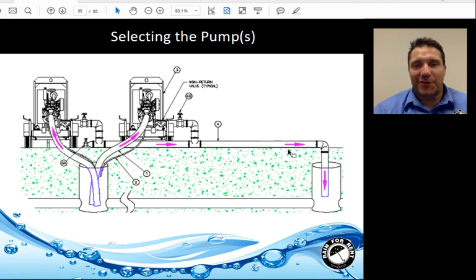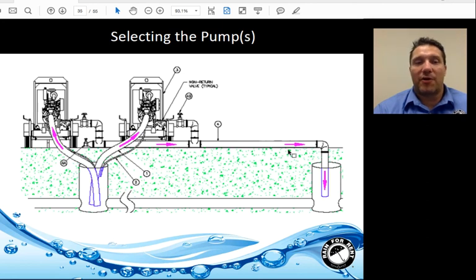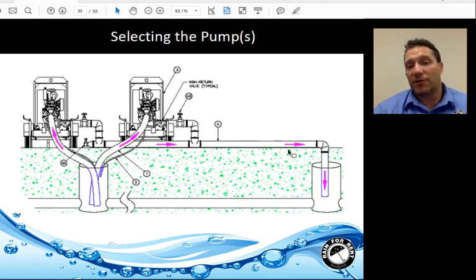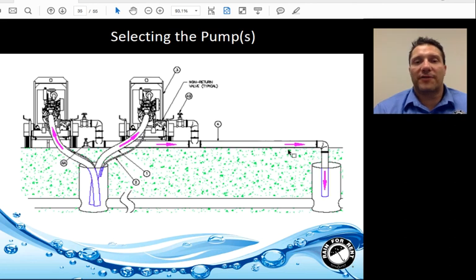A two-pump setup should include a primary pump and a backup pump, both with independent suction lines. Both pumps are manifolded with isolation valves into a common discharge line that goes to a single open discharge point. The isolation valves allow each pump to be separated from the system — for example, for maintenance or deragging operations.